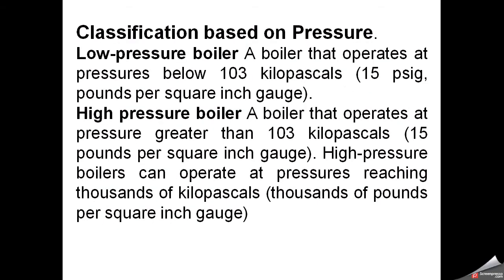Classification based on pressure. Low pressure boiler operates at pressure below 103 kilopascal or 15 pounds per square inch gauge. High pressure boiler operates at pressure greater than 103 kilopascal or higher than 15 pounds per square inch gauge.